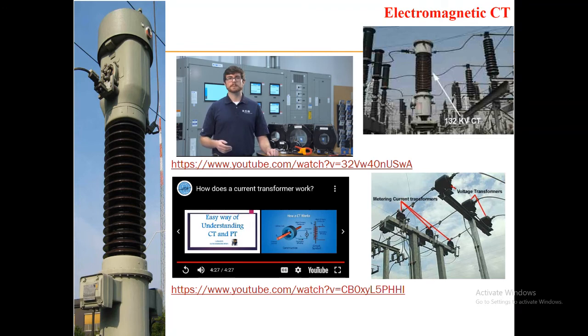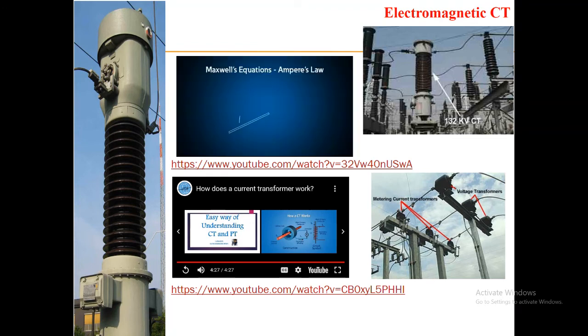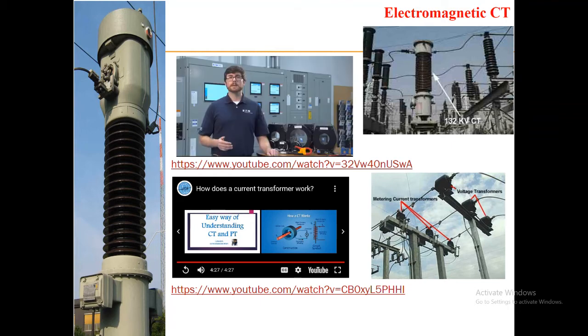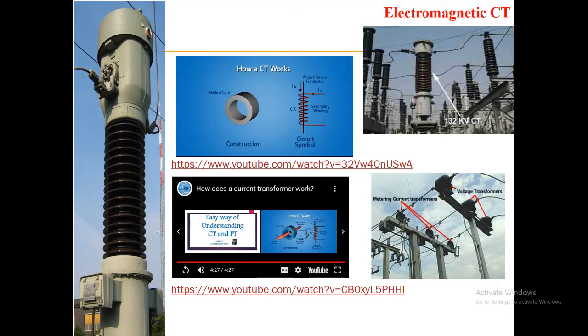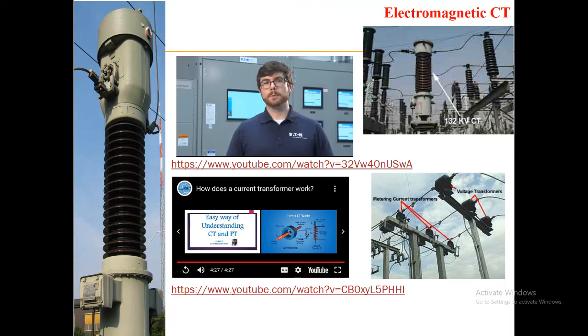Let's start with a simple explanation that describes the most common ways of calculating and measuring current using current transformers. By applying Maxwell's equations, specifically Ampere's law, we can say that if a magnetic field is integrated around a closed loop of wire, the value of that integral is equal to the net current enclosed by the loop. CTs are closed loop instruments consisting of a magnetic core and a secondary winding around the core. The primary winding of the CT, the main loop, has the wire with the current we wish to measure pass through the center of the core. The primary winding that carries the main current is said to have a single loop or winding. The wire produces the magnetic field that drives the current on the secondary winding, which is used as the output of the CT.